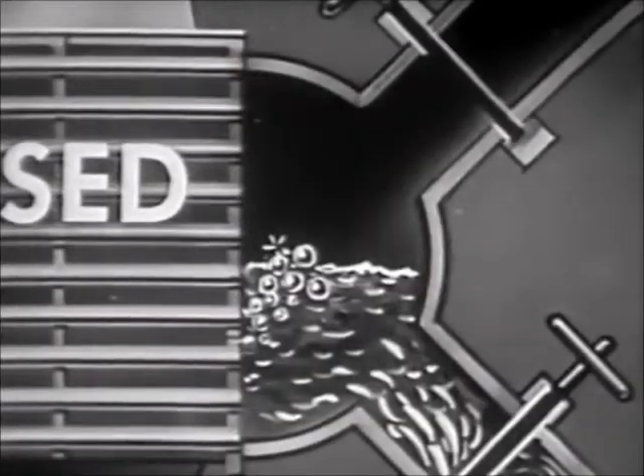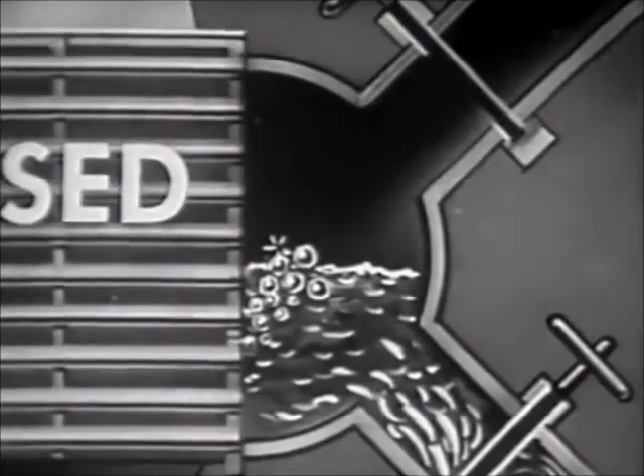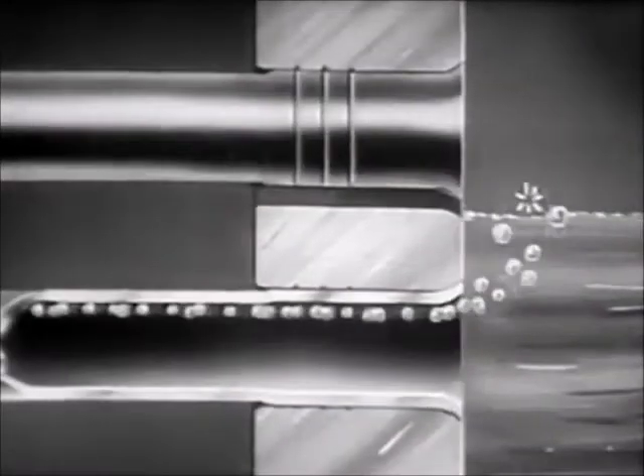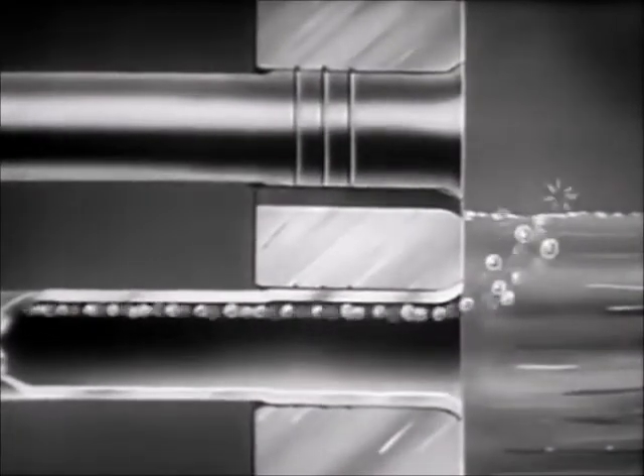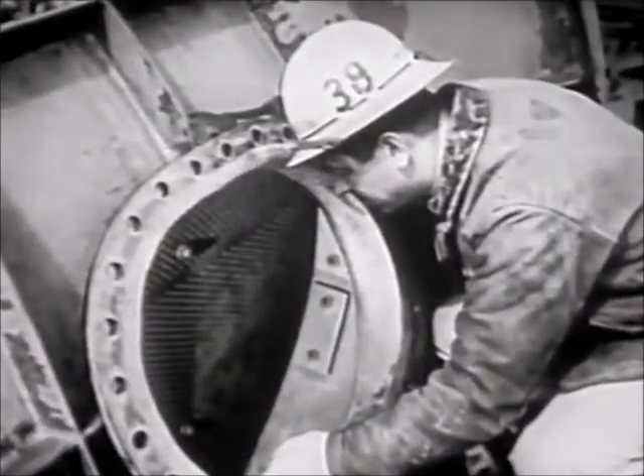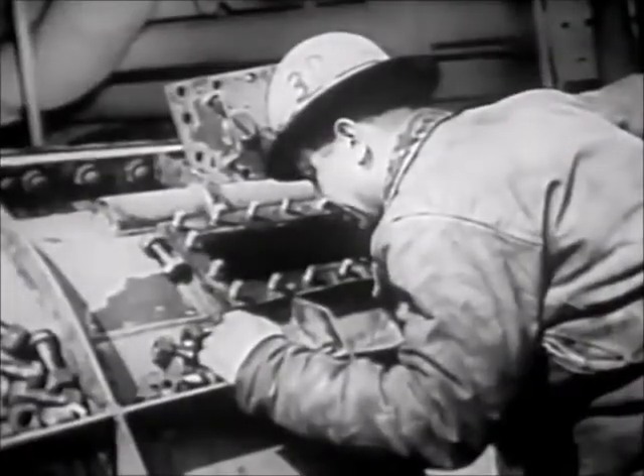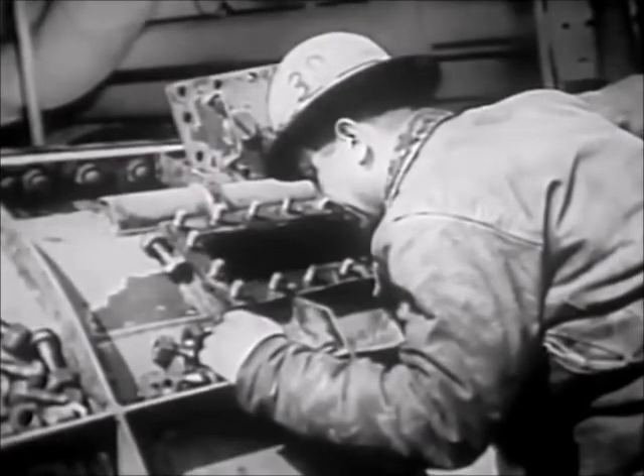When the water covers a leak, the compressed air bubbles up in the water chests. You can trace the bubbles either directly to a leak or to a tube which is leaking. Watch for bubbles through openings in both water chests. As the water rises, close the lower openings and continue observation through openings higher up.